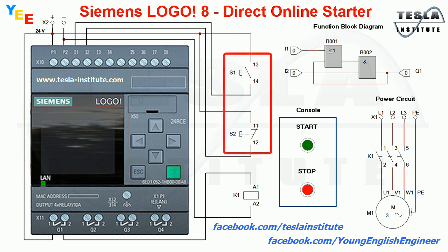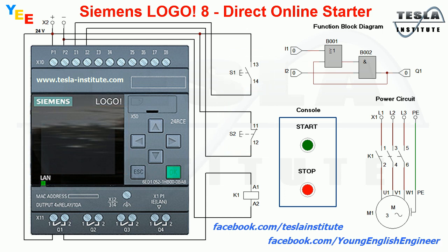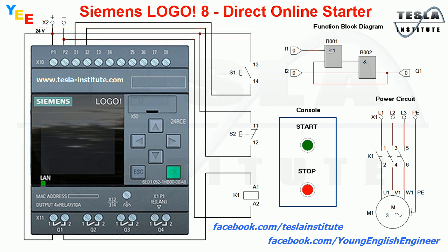In the control circuit we use 2 push buttons. The normally open push button S1 is used to start the motor. This button is connected to the plus of the 24 volt power source and to digital input I1 of the Logo controller.